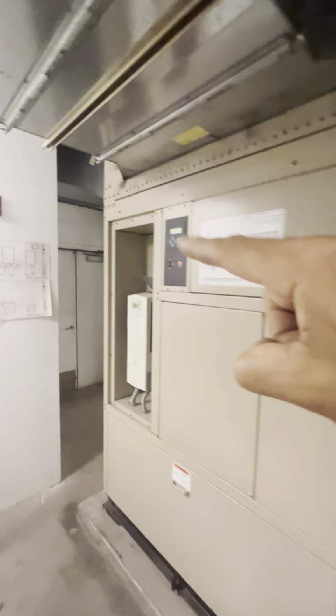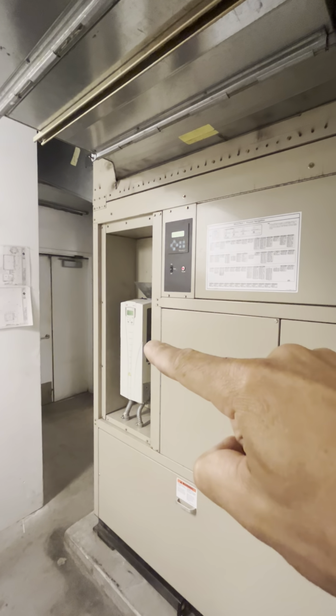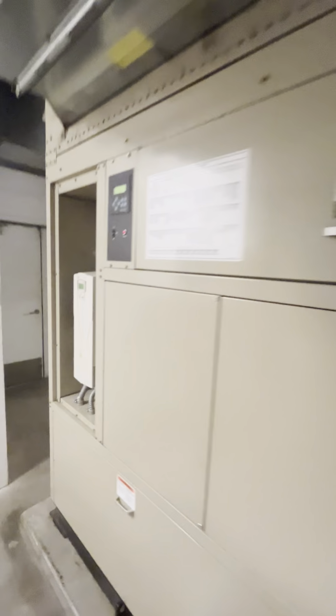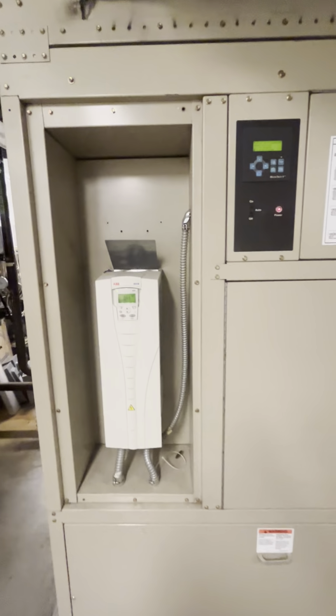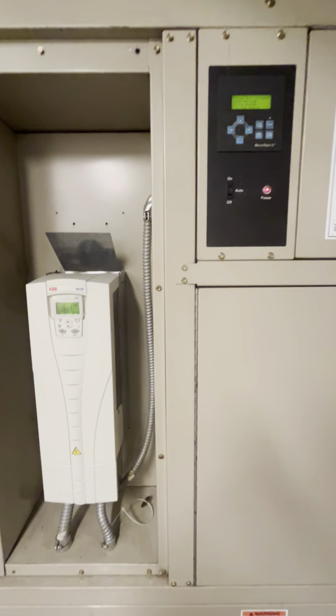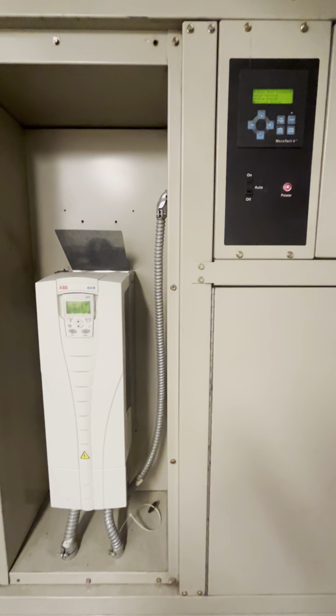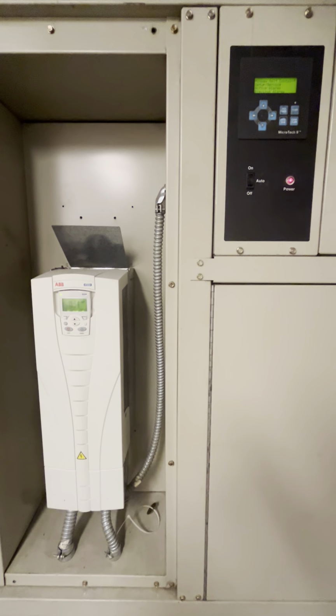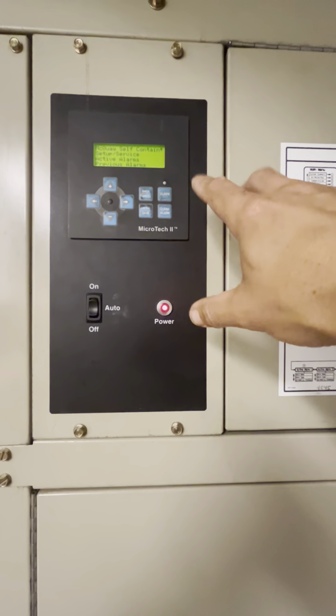You have two screens over here, your Microtech and your VFD. Wait for those screens to go completely blank. Wait about 20 seconds, then come back over here, flip this back up, and these will go through a whole startup process. The whole process itself takes about 5 minutes to get the machine back going again, so just be patient with it. During that process, some alarms may pop up. As they do, just clear them. It's just the unit starting up.